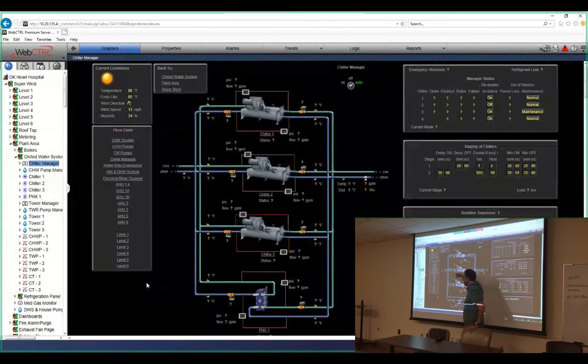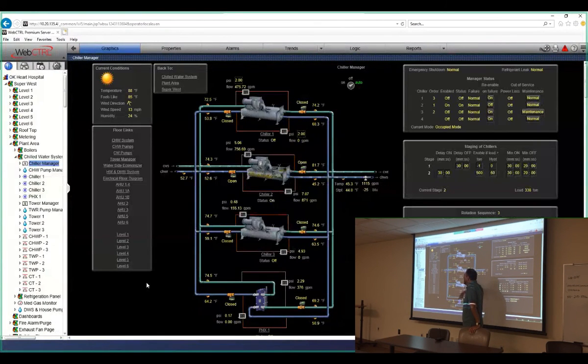At design flow, with these differential pressure transducers across the barrels, when we're at the right flow rate, it should be pretty close to what is designed on the chiller. So if design at the chiller is 5 psi on the condenser water barrel for 1200 GPM, and we have one pump running at 1200 GPM, you should be somewhere around 5 psi. It's going to fluctuate because we're dealing with a pressure transmitter and turbulence and everything else, but it should be pretty close. Your chill water side differential is going to go up. Design may be 7 or 8. Okay, so we're at 7. This is a calculated number.